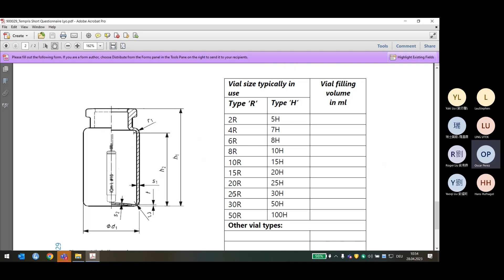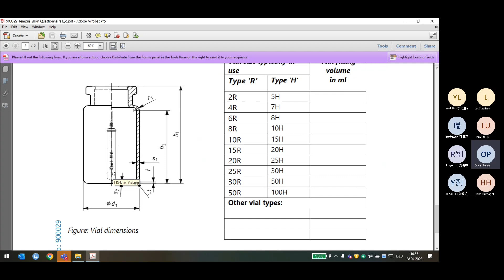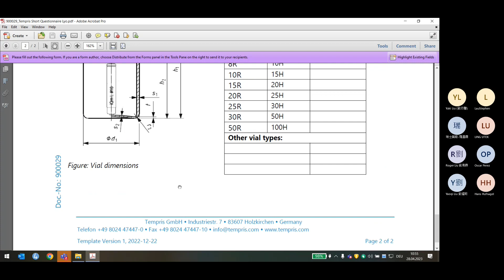We saw here the volume of the sensor inside the vial, and we think the volume of the liquid will grow a lot, but it's really just a few millimeters, around 0.1 millimeters, when we immerse the sensor in the vial. The measurement point is 2.2 millimeters in diameter and the body is 4 millimeters, I think. So it's a very thin sensor, specially designed for lyo products. So these are the short questions. Then we have an extended one when we go forward, but for an initial proposal, this should be enough.